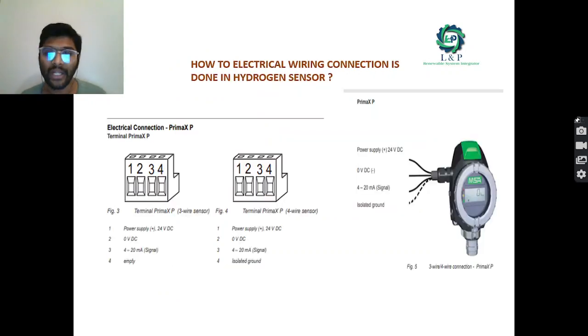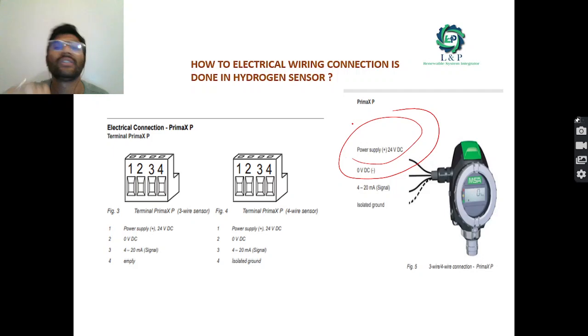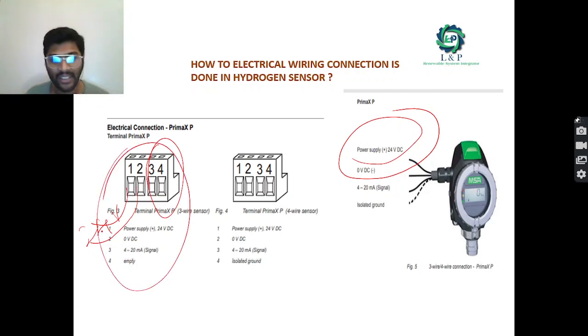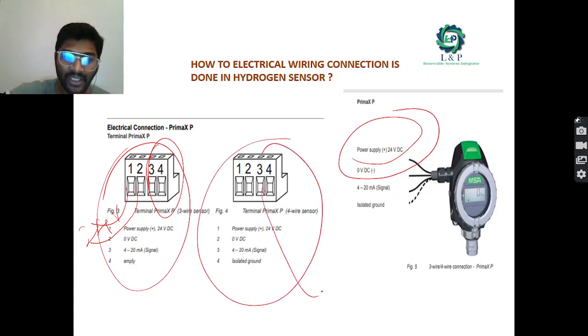How to do the electrical wiring? As we said earlier, for the device to work, it needs a power supply. What power supply are we going to use? We are going to use a 24-volt power supply. Terminals 1 and 2 are for the power wiring, that is 24-volt. If you want to take the output, you can use terminal 3 and the common. If you're going for a 3-wire connection, you can use this sort of wiring, and if you're going for a 4-wire connection in the PrimaX P, you can do this. Terminal 3 will be connected to your signal cable, that is the 4 to 20 milliamp cable, and 4 will be the ground. Most importantly, whenever you are using any sort of cables for the sensors, please use shielded cables.